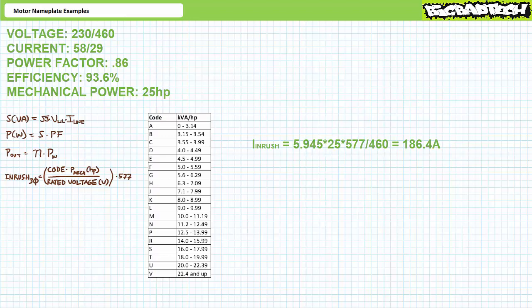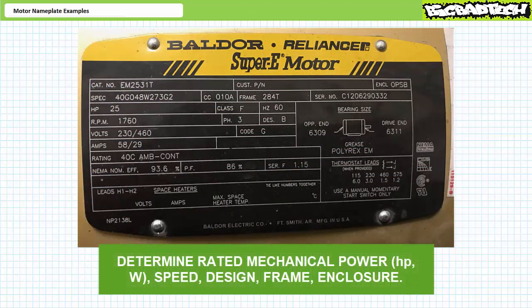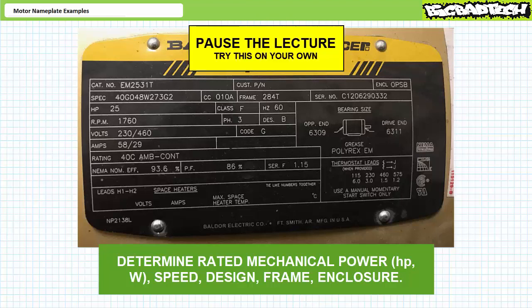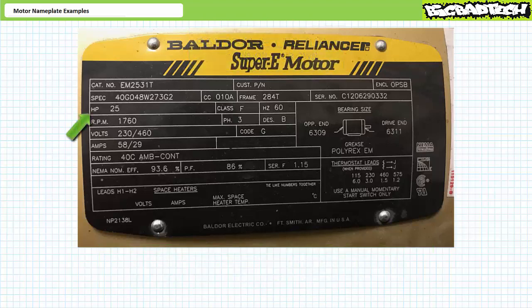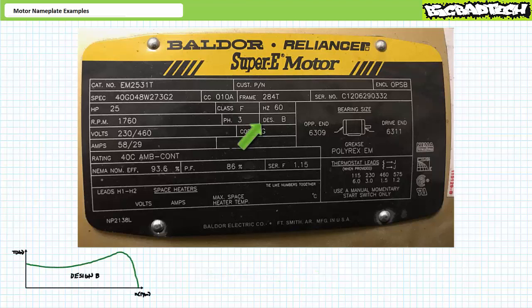Let's take a quick look at some mechanical characteristics. See if you can determine the rated power in horsepower and watts, rated speed, design, frame, and type of enclosure. Pause the lecture and try this on your own. It looks like this is a 25 horsepower motor operating at a rated speed of 1760 RPM. A unit conversion shows 25 horsepower is roughly equivalent to 18.7 kilowatts. This is a NEMA Design B general purpose induction motor, which has a characteristic speed-torque curve.